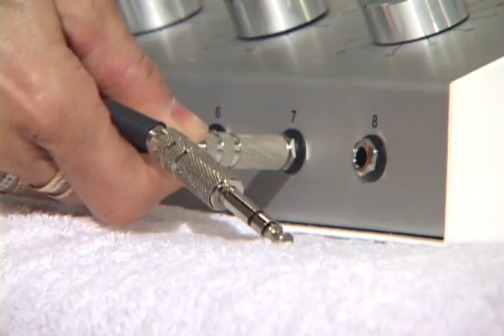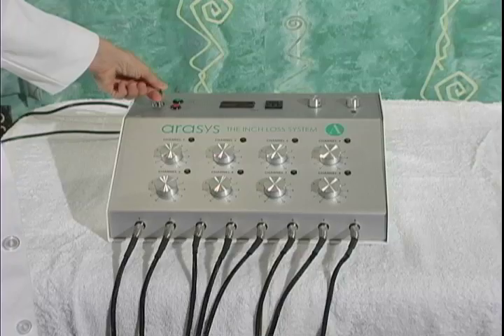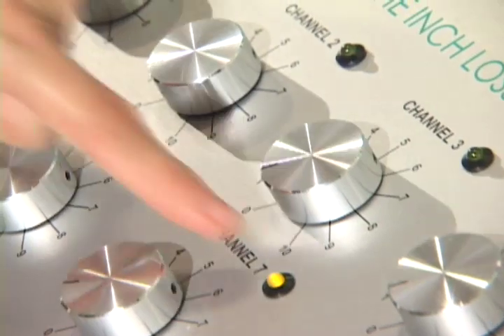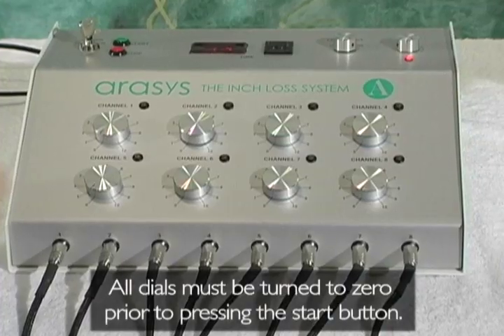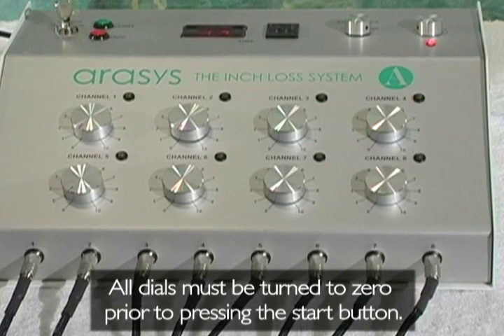Preparation: Step 1 — Plug the arasys cables all the way into the ports. Step 2 — Turn the key to the on position from left to right. Step 3 — Adjust the timer to 17 minutes as desired. Step 4 — If any of the lights next to the dials is on, turn that dial to zero. You must turn all dials to zero prior to pressing the start button. If all dials are not turned to zero, the machine will not go on.